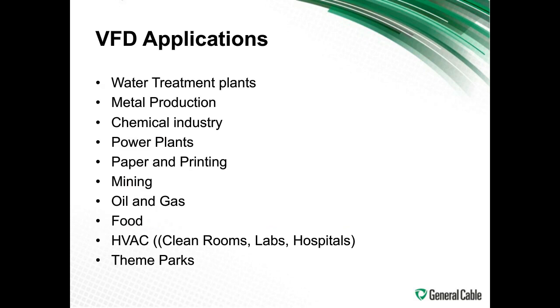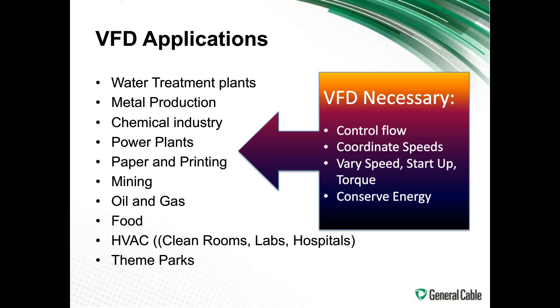And we are seeing more and more applications in using VFDs for many different industries: water treatment plants, metal production, chemical industry, power plants, paper and printing, oil and gas, mining, food, clean rooms, hospitals, theme parks even. The main reason is to control flow, to coordinate speeds, to vary the speed, startup and torque, and to conserve energy. So anywhere where you can actually manipulate the drive, the motor speed, you need to use a VFD.